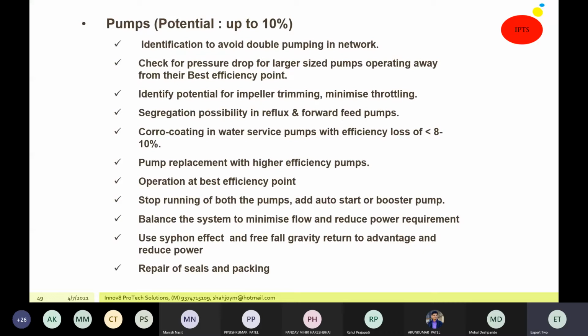Say in the industry, if you go, almost 10% potential is there in the pumps for energy consumption. Look at any pumps, you will find several locations where double pumping is taking place. In several places you will find the pressure drop is very high in the pipeline. Sometimes you will find very high head is developed although it is not required, where you can do some impeller trimming. There are several locations where some segregation can take place so that your pumping requirement can be reduced. So if you see a complex process, all these things will be applicable.